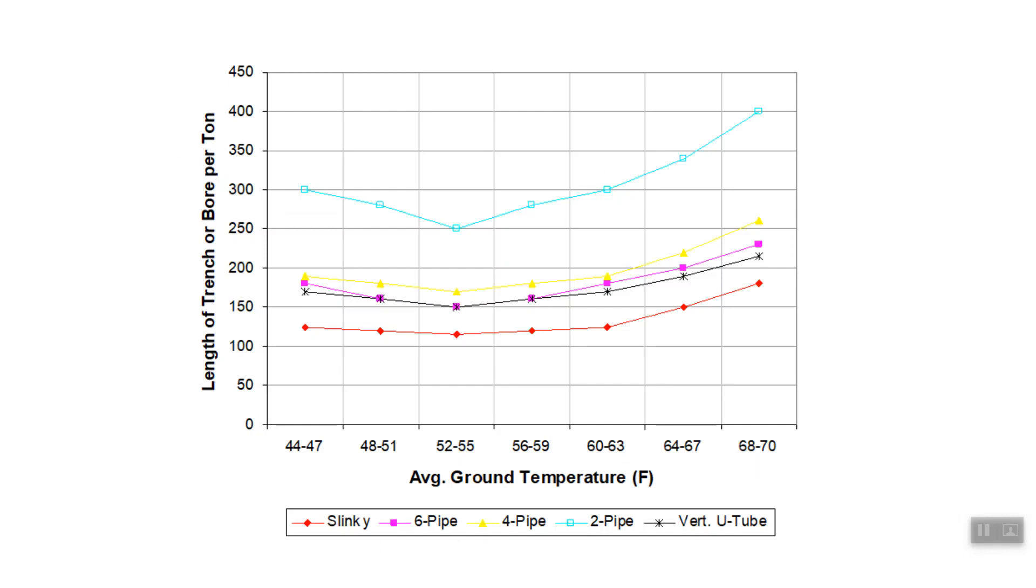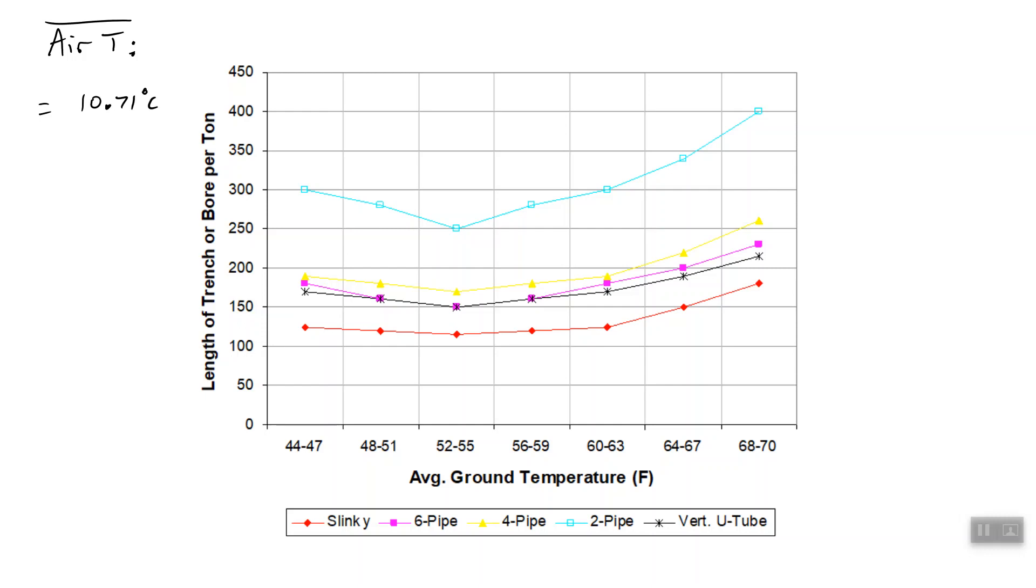So let's talk about that. The average air T that you get if you use TMY3 data for the Dayton airport, the dry bulb column, averaging just in Excel, you know, type equals average, and then put in the entire column, whatever that column is. Then you get 10.71 degrees Celsius. So that's the average air temperature in Dayton, Ohio, over the course of an entire year, which correlates to the average temperature in the ground.